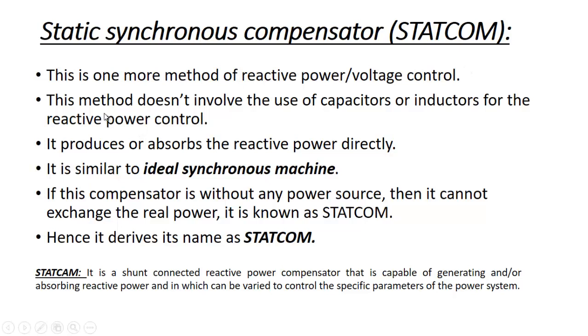By drawing leading or lagging current, STATCOM is able to control the reactive power — it can both produce and absorb reactive power. It is similar to an ideal synchronous machine, which is why it gets the name 'synchronous.' It is called 'static' because the normal synchronous machine is a rotating machine while the STATCOM is static. As with a synchronous machine, it does not have inherent capacitors or inductors. If the compensator is without a power source, it cannot exchange real power.